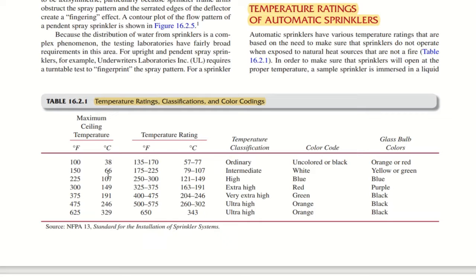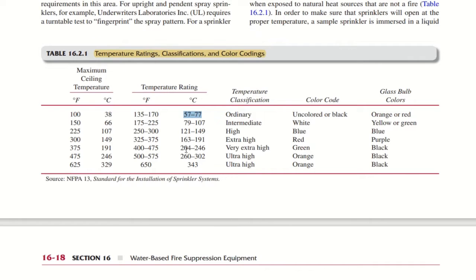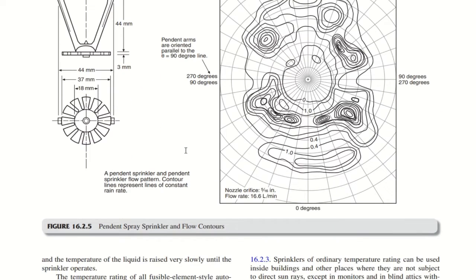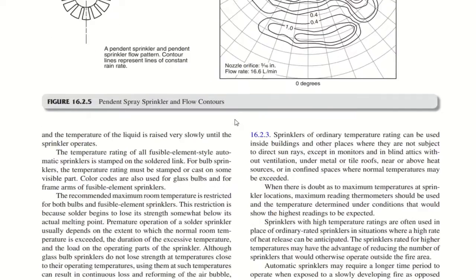So if the ceiling temperature, for example, in general you have 38 degrees maximum ceiling temperature, then we can go with the orange or red color bulb type of sprinklers with the temperature rating between 57 to 77 degrees centigrade. So basically we'll go with the 68 degrees centigrade temperature rating, considering the red color bulb, since that is available in the market, and that is a very important topic, so you need to go through it thoroughly. Here they have provided the pendant sprinkler pattern, the pendant type of sprinkler.